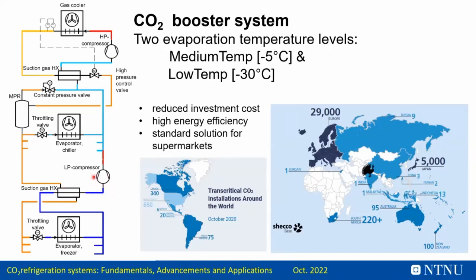Typically you have a low pressure compressor, a high pressure compressor, and rejecting the heat after heat recovery, which is normally placed here. You cool down the gas further in a suction line heat exchanger, and the high pressure control valve flashes the gas into a separation tank. The constant pressure valve keeps the pressure level in this tank and mixes what comes from the low pressure side towards the suction line to the high stage compressor.